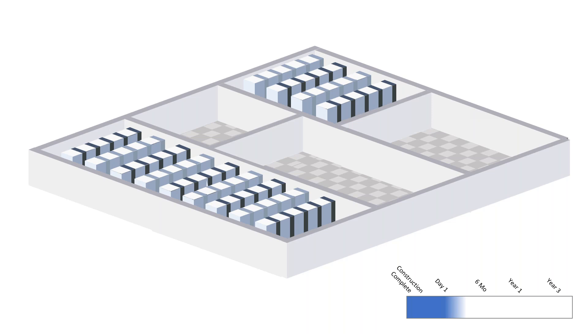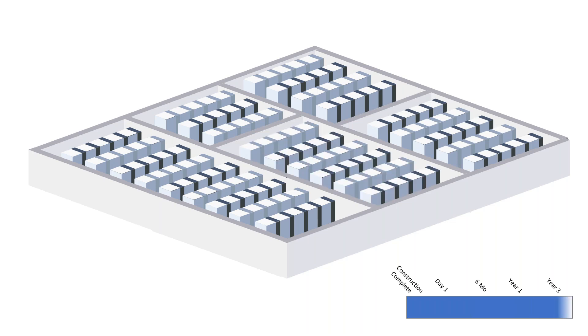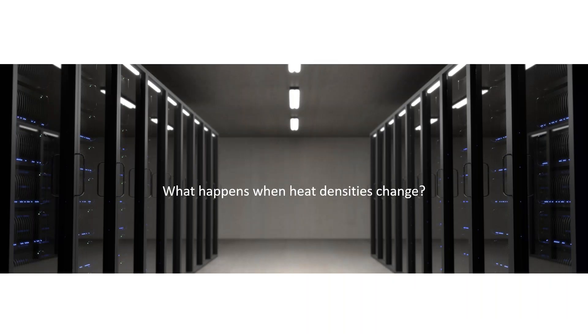On the first day maybe we have a few people who get their equipment in place. Six months in we get a little bit more fill, within a year we're mostly full, maybe in year two or three that data center's full and chugging along. The point is, if we think about a standard commercial HVAC project, our load shifts from minute to minute. But at the data center, minute to minute the loads aren't changing very frequently, but over time they definitely are, whether it's moving computers in and out of our space.